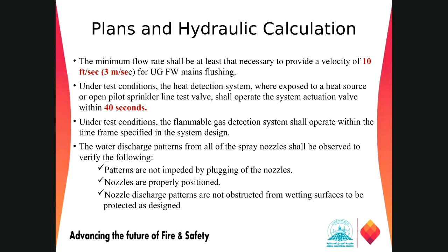And nozzle discharge patterns are not obstructed from wetting the surface to be protected by design. What they are talking about is, suppose this needs to be protected by something, and there we have some column, right? Where we have some column, and our nozzle is at this location. So the water pattern might not reach this area because of this obstruction.